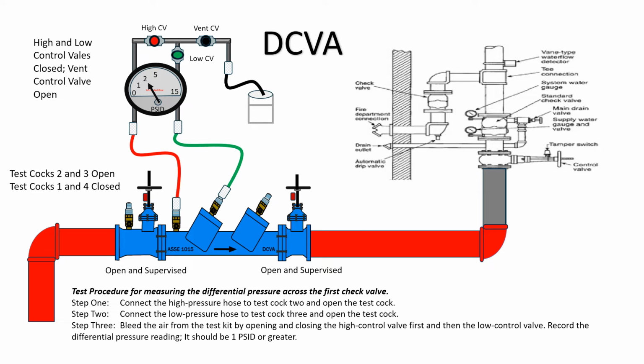Test procedure for measuring the differential pressure across the first check valve, DCVA. Step 1. Connect the high-pressure hose to test cock 2 and open the test cock. Step 2. Connect the low-pressure hose to test cock 3 and open the test cock. Step 3. Bleed the air from the test kit by opening and closing the high control valve first, and then the low control valve. Record the differential pressure reading. It should be 1 psid or greater.